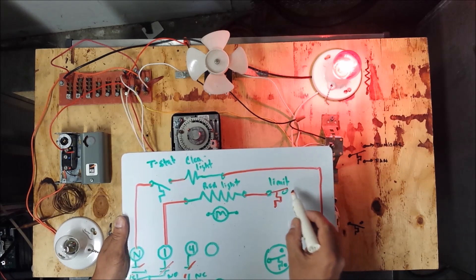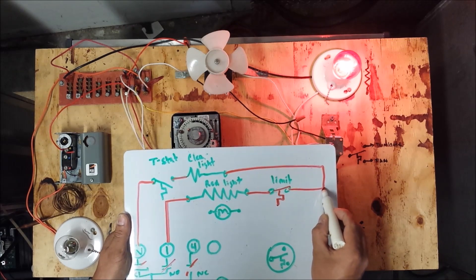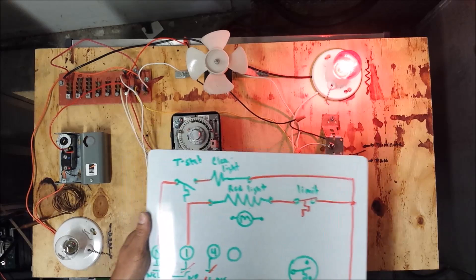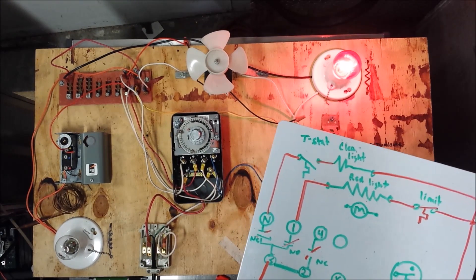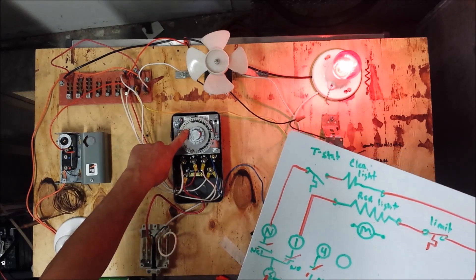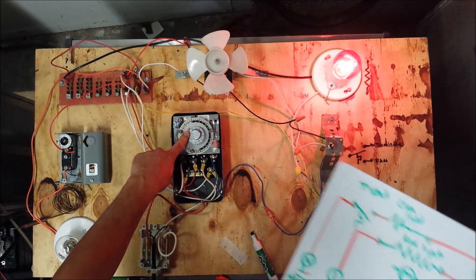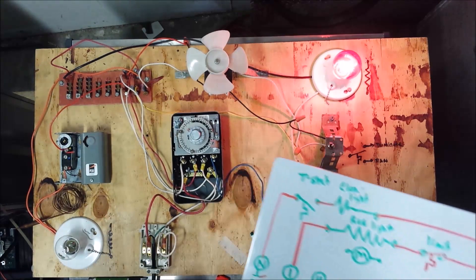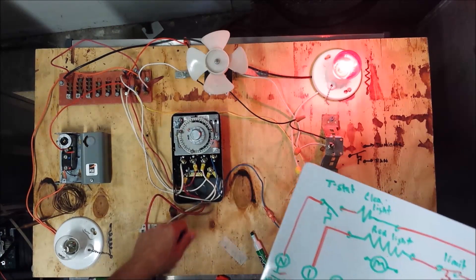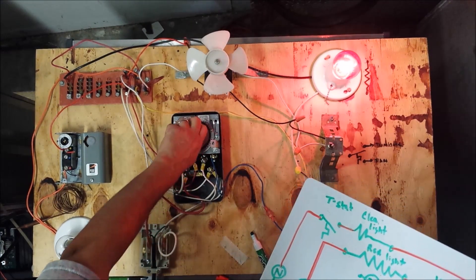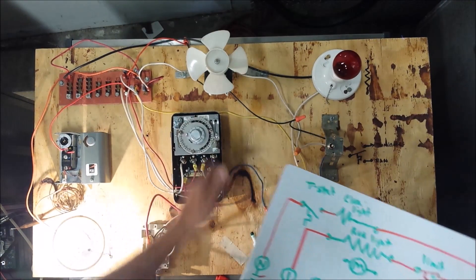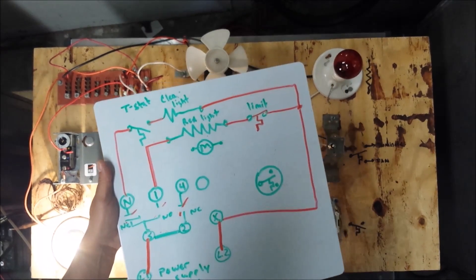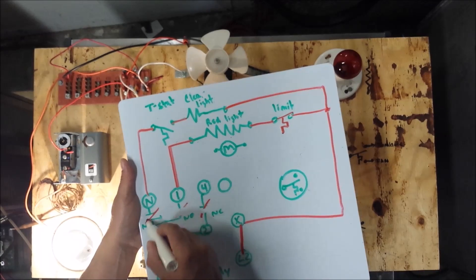In order to make that circuit work, it has to go back to L2, which this does. Once the defrost has completed — either by time duration or by our defrost terminator — defrost will end. We advance the timer to kick it out of defrost, and now our defrost terminals have opened back up and our normally closed switches have reclosed.